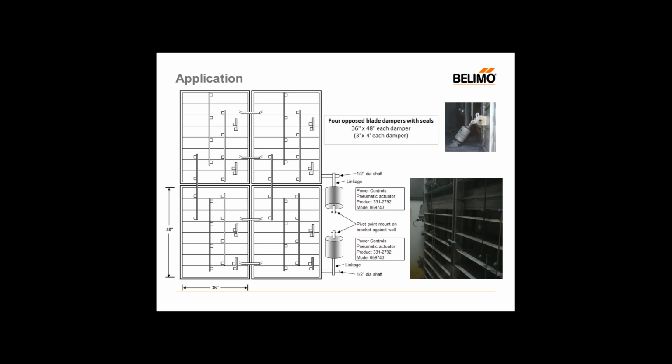Moving on, looking at the first application here, it's a typical application that we've come across in the past, where we assisted a customer in replacing some older pneumatic type actuators. You can see the photos here on the left and on the right. I'm showing a typical assembly we came across on an air handler, and the information that was provided to us in terms of the physical aspects of the damper. But of course, there are other conditions and other things that apply when you properly size the damper actuator.